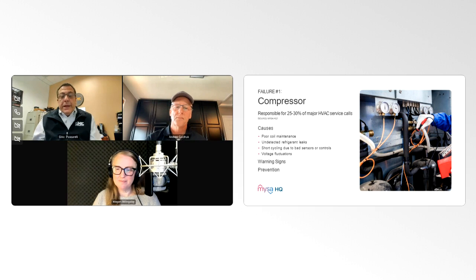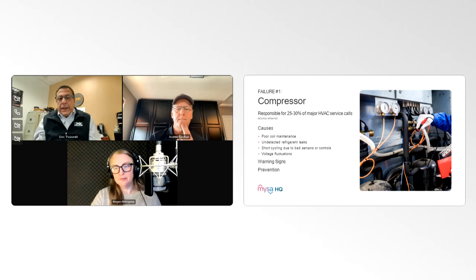Gino, any thoughts? Yeah, I agree with Andrew. From an FM standpoint, one item that could be addressed to take a proactive approach, if you don't have the ability to view the set points and actual temperature in the space from one location, is to do a daily walk. Let's look at your thermostat, see if you achieve that set point and things of that nature, so you can catch if there is a problem before that problem becomes a drastic problem.